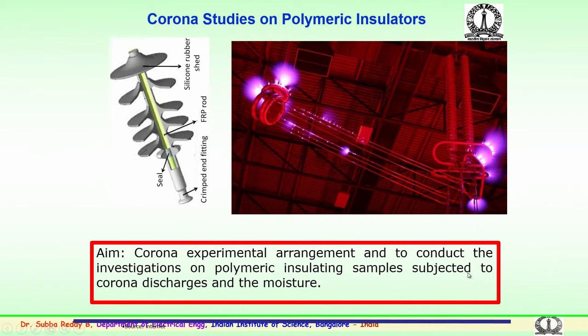So, it is expected that a corona experimental arrangement is used to conduct the investigations, particularly on polymer insulating samples. Either full scale insulators or flat insulator samples, made of the same material which is used for manufacturing the actual insulators, will be used for the study.